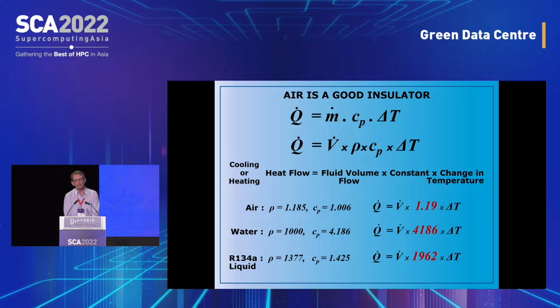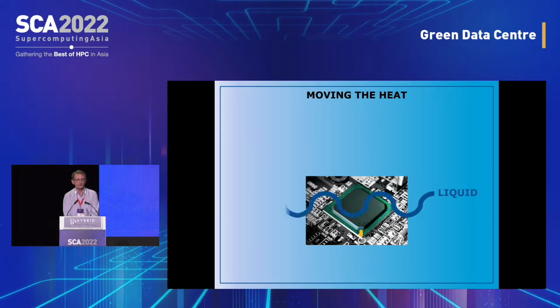So let's look at that in practice, putting liquid across the chip to take away the heat. Once we use a liquid instead of a gas, to get our 75 degree chip surface temperature we don't have to have the liquid so cold, it doesn't need to be 25 degrees anymore. In fact, if we used 40 degree liquid, the heat exchange is so much better that our chip surface actually becomes cooler. So we get an advantage doing this, where the heat transfer is so much better the chip is kept cooler, meaning the processing is done better and you get better performance on your processors. This is the fundamental idea behind liquid cooling.